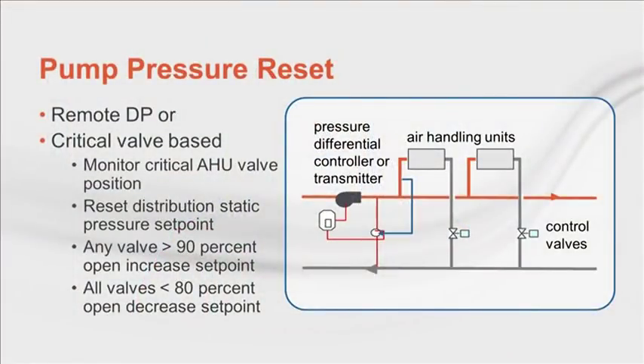Pump pressure reset results in slowing down the pump on the secondary side, either based on remote differential pressure or based on critical valve position. On systems with pumped coils, you might look at the highest pump speed. As the load falls and the fan speed turns down to a certain point, controls for the terminal or the air handler begin to close the chilled water valve. The pressure upstream of it goes up, and nearby valves see an increase in pressure too. In turn, they'll close if it results in overcooling.